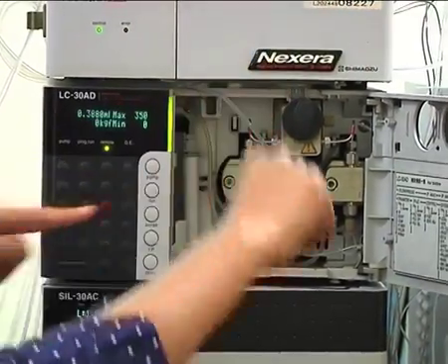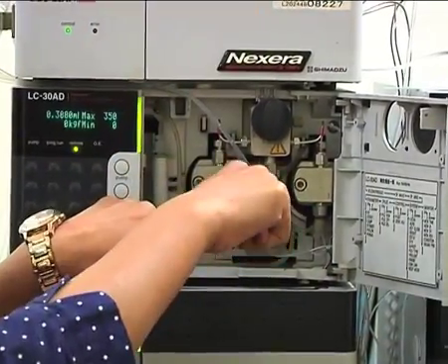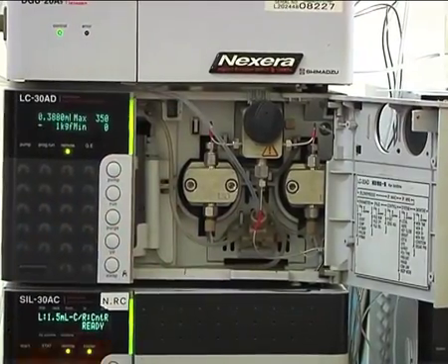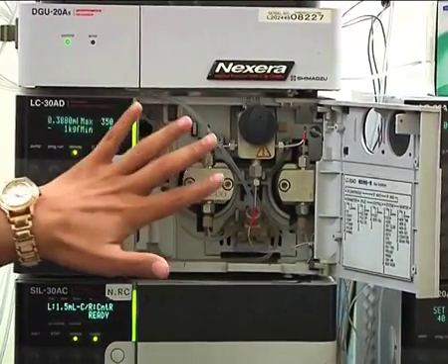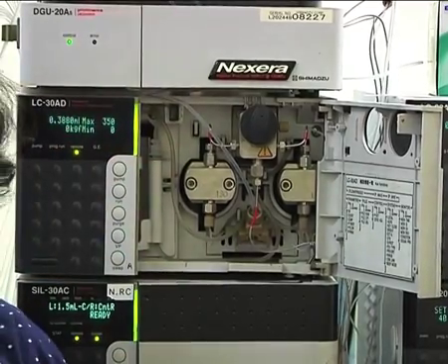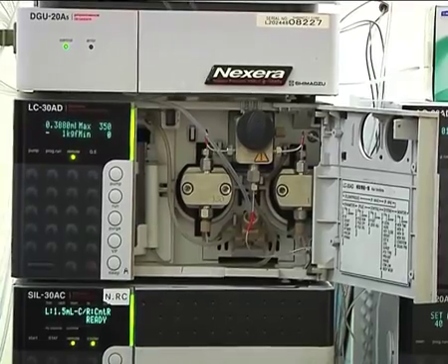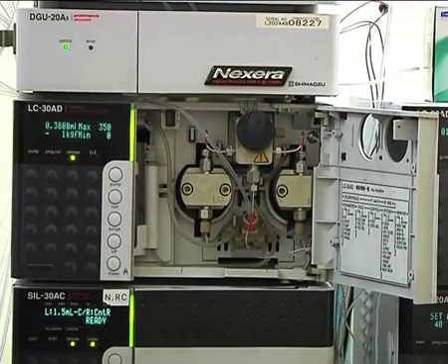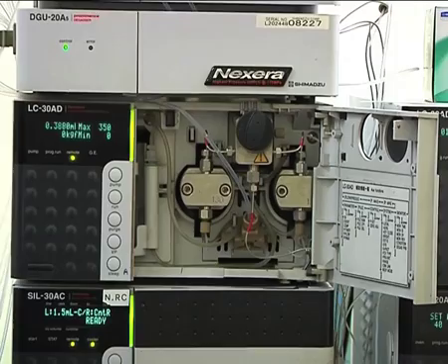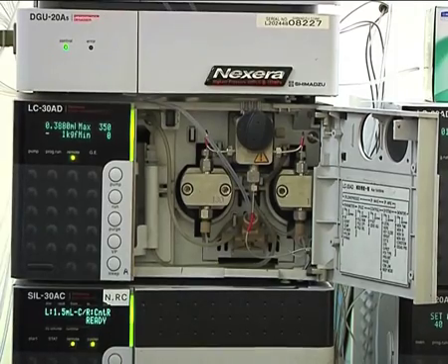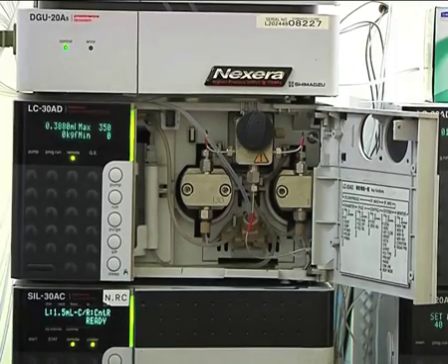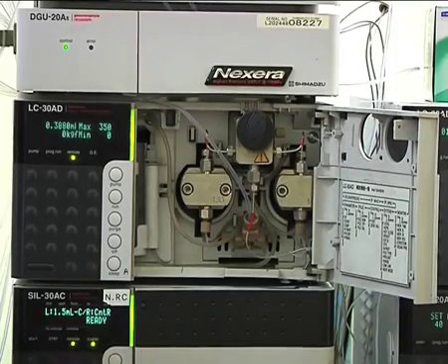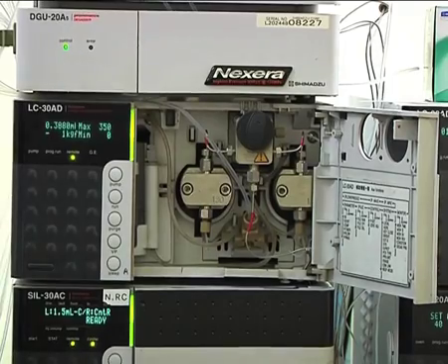So when this is passing mobile phase to the column, this will get refilled with the mobile phase and vice versa. Okay. The back pressure withstanding capacity of this particular model is 19,000 psi, 130 megapascal. So you can use higher flow rates as well. You can use smaller particle size columns and smaller ID columns, which normally tend to generate higher back pressure, but still those can be used on this particular system.